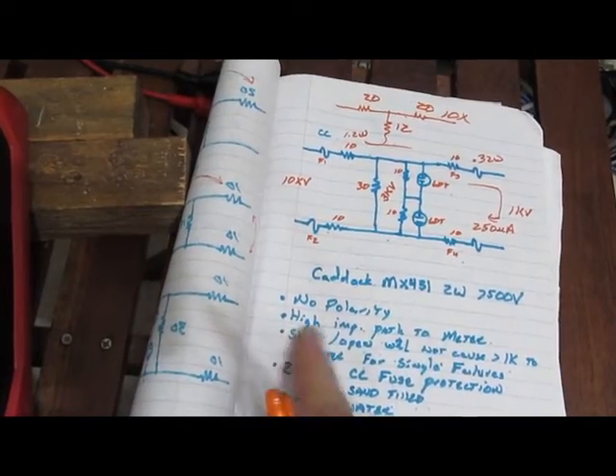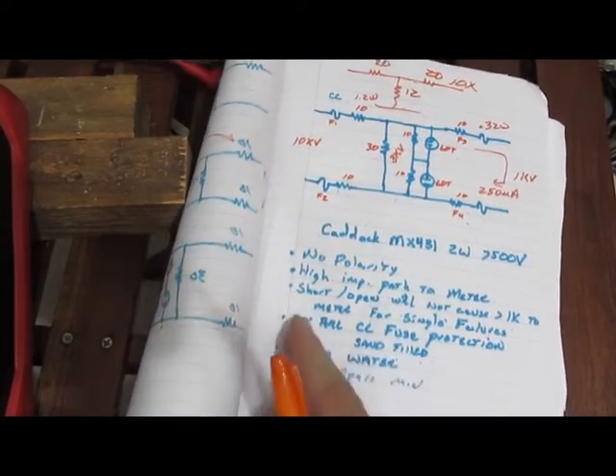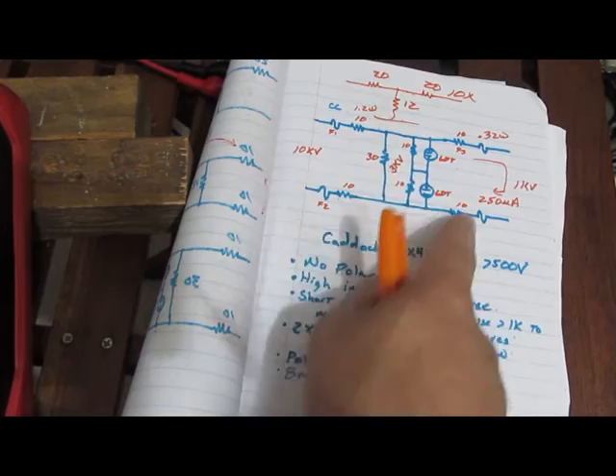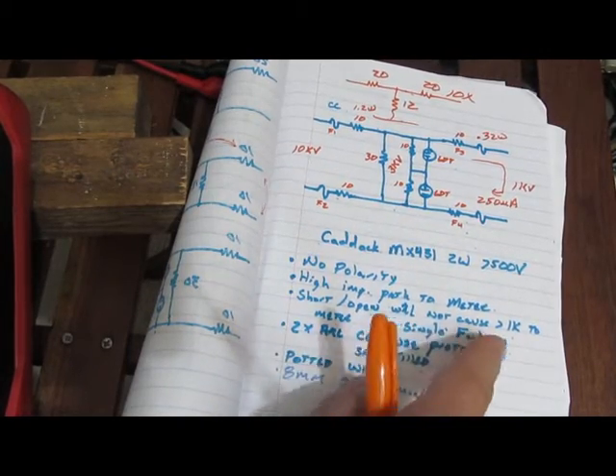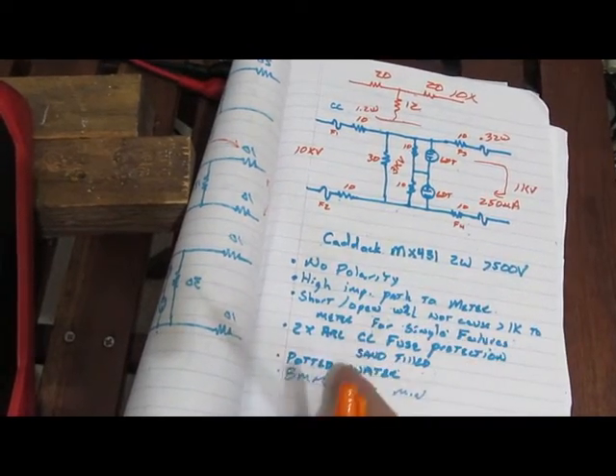Again, there's no polarity - it's a high impedance path to the meter. A short or an open on any component in this circuit is not going to cause the voltage at the meter to exceed 1 kV.